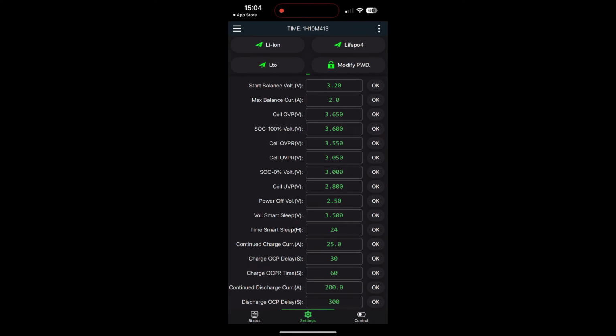Okay, so let me explain how this BMS is now going to work, right? On the discharge side of things, it will basically come down, and as soon as it hits the SOC 0% of 3 volts, it will not allow any more current to be discharged out of the battery bank until it hits 3.05. And at that point, it will hit the under voltage protect reset, and it will allow discharge to start happening again out of that battery bank. Okay, it'll still allow charge to go in, it just won't allow any charge to be coming out.